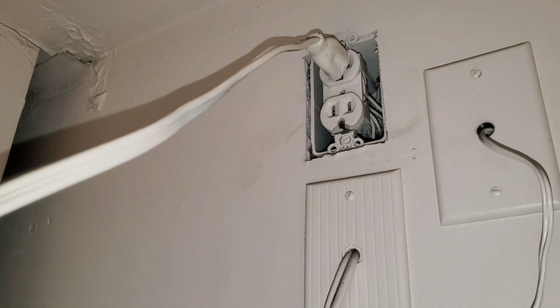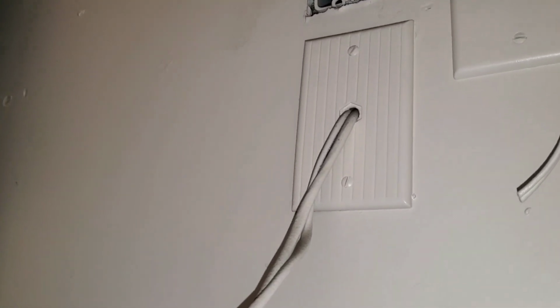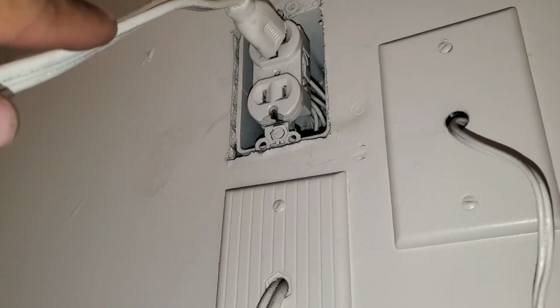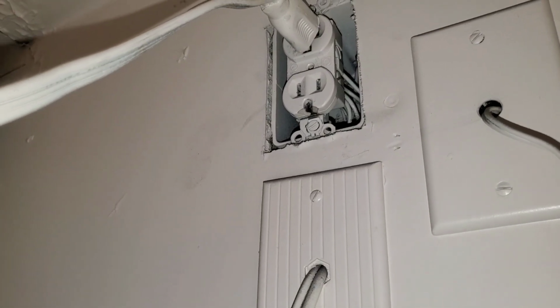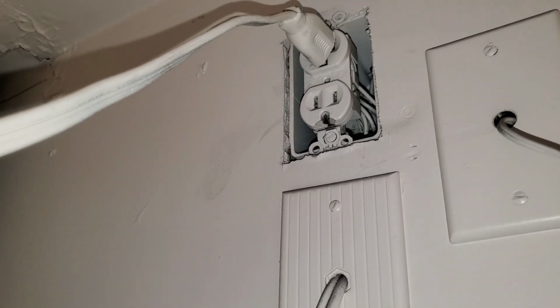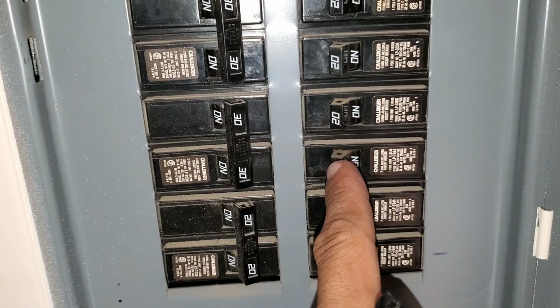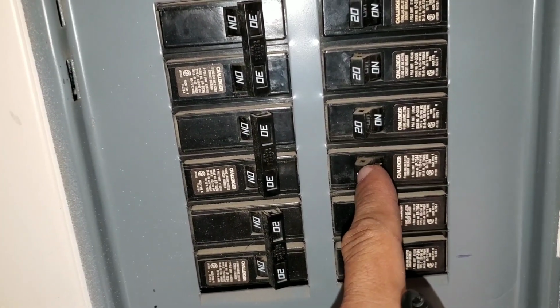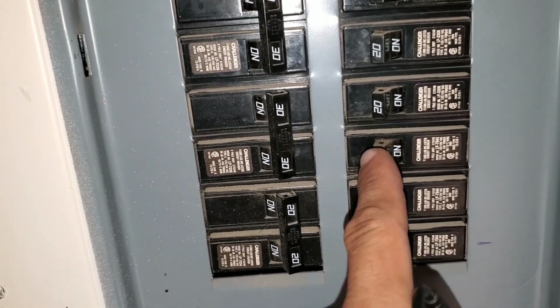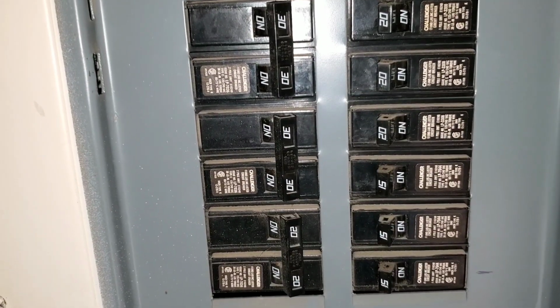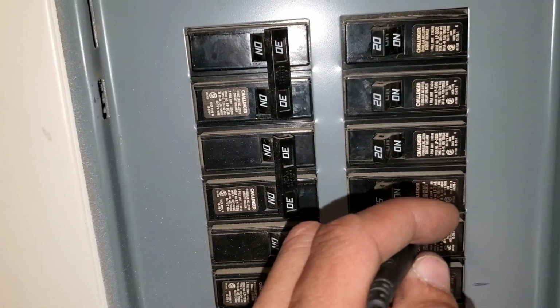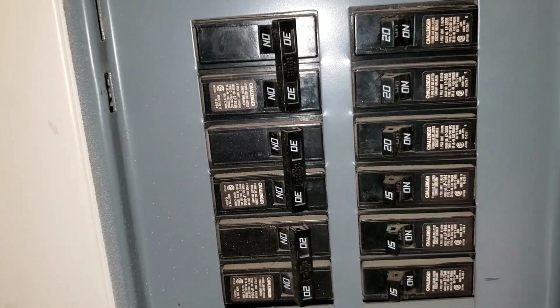Now sometimes it is a plug-in, sometimes it's a switch, and you'll want to either unplug your switch and check the voltage, or you'll want to remove the switch and go ahead and check the voltage. You can see here that I do not have voltage. If you check your breaker and your breaker is set to the on position and it's not tripped, most likely you have a faulty breaker. I do have a video posted on my channel showing you how to test and or replace a faulty breaker.